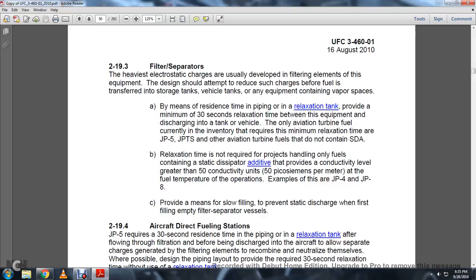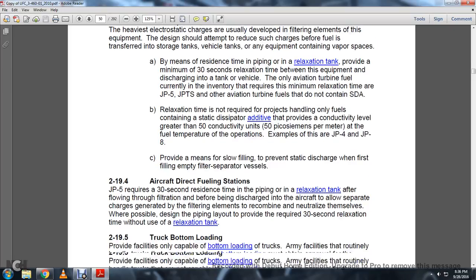The relaxation tank design is not required for projects handling only fuels with the static dissipator additive that provides a conductivity level greater than 50 conductivity units, with 50 picosiemens per meter at the fuel temperature of operation. Example, JP4 and JP8. Provide a means for slow filling to prevent static discharge when first filling the empty filter separator vessels.